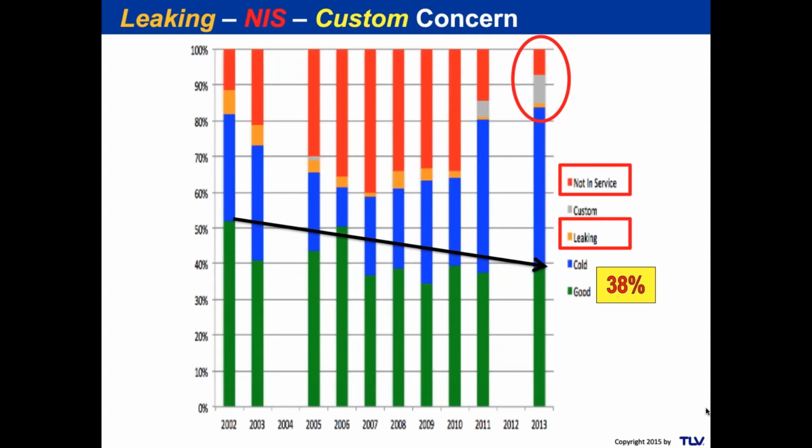That's actually pretty good. So this site, because they have so many blue cold failure traps, I would expect to see a lot of hammer on the steam supply and on steam equipment, problems with flares, problems with turbines. But because they only have 2% of the traps leaking, I would not expect to see a lot of problems in the condensate return headers.